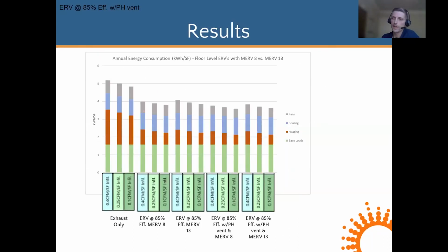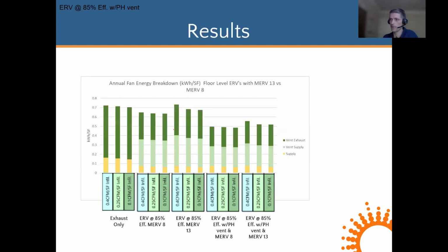All right, then we wanted to compare what happens if we increase the filtration. If we want to have better indoor air quality, we increase the filtration to MERV 13s. Here's the energy consumption. We can see very small increase in energy consumption here between MERV 8s and MERV 13s. Only the fan power really is impacted. So if we look at the fan power, this is the fan power alone. You can see between MERV 8s and MERV 13s, there is an increase in fan power, which makes sense. We have 4 filters on each airstream in an ERV. The fans have to work a lot harder to overcome the increase in static pressure.